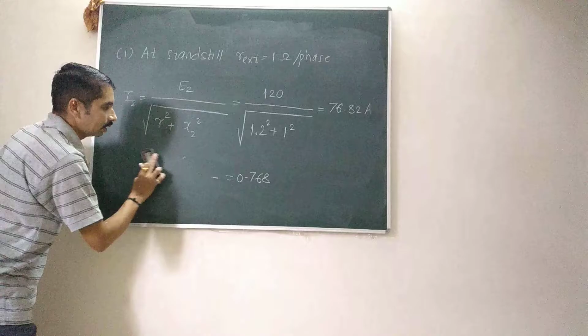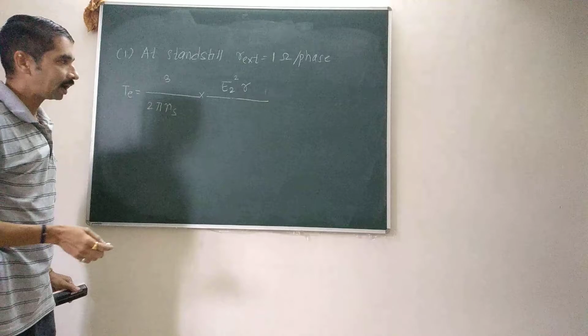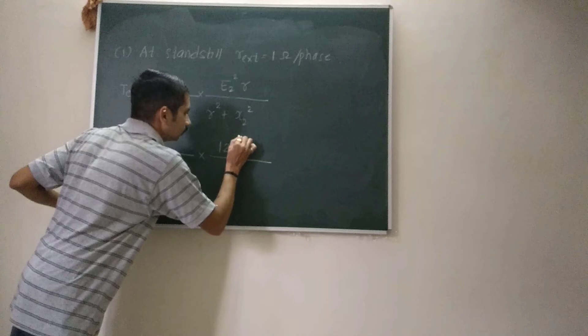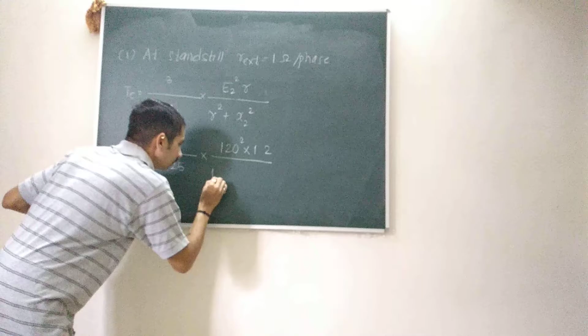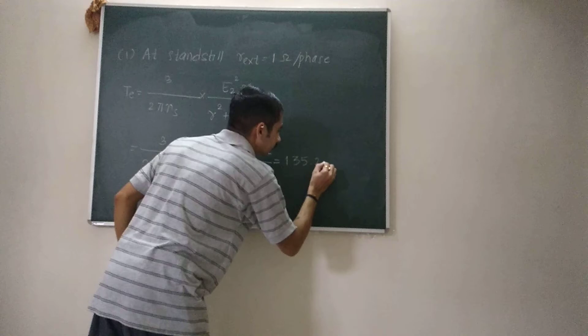And the value of torque upon addition of 1 ohm resistance per phase will now be Te is equal to 3 over 2 pi Ns multiplied by E2 square into the new value of rotor circuit resistance per phase, that is R, divided by R square plus X2 square. So it will be 3 over 2 pi into 25 multiplied by 120 square into 1.2 divided by 1.2 square plus 1 square. You will get the value as 135.25 Newton meter. So please check whether you are getting a similar value for the electromagnetic torque upon addition of a 1 ohm resistor.